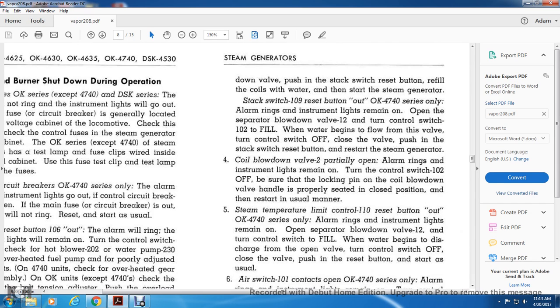Reset button out with the OK 4740 series only. Alarm rings, instrument light remains on. Open the separator blowdown valve 12. Turn the control switch 102 to the fill. When the water begins to flow with the valve open, turn the control switch off. Close the valve, push in the stack switch reset button, and restart the steam generator.